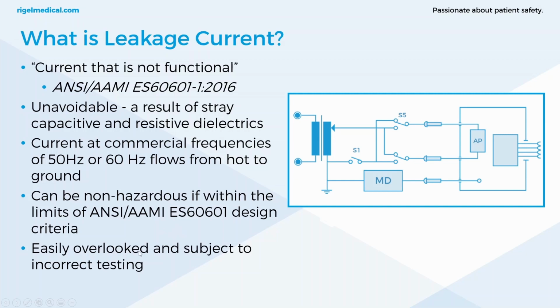But during development of these medical devices, the high levels of isolation from any electrical potentials to any accessible conductive parts is a big requirement for the medical device manufacturers. And the standards do have rigorous statements that say that the device must have certain levels of isolation, degrees of spacing, and that just ensures that leakage limits are as low as possible.